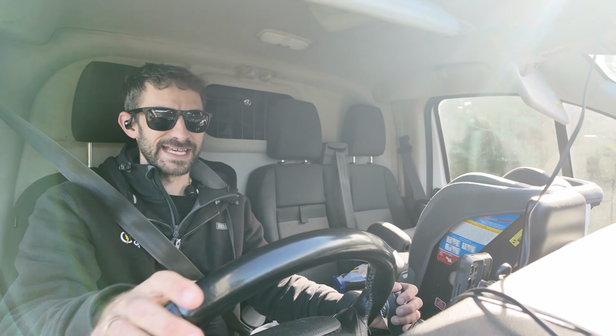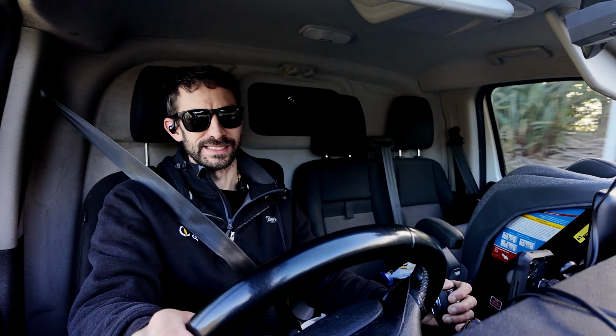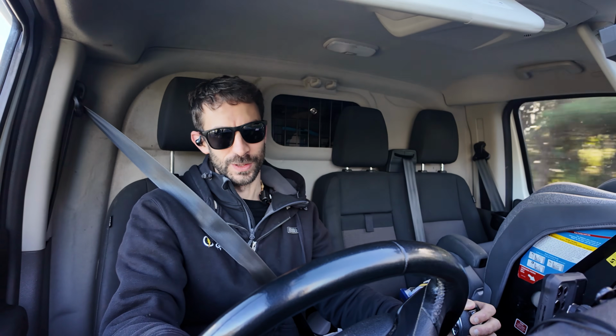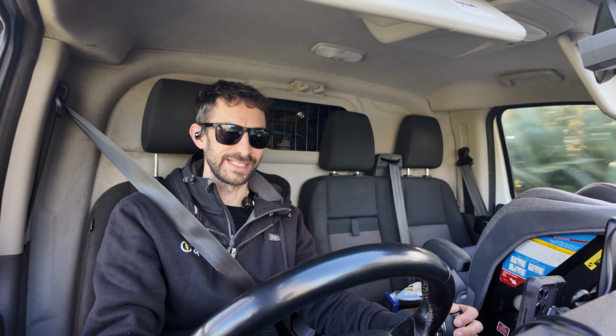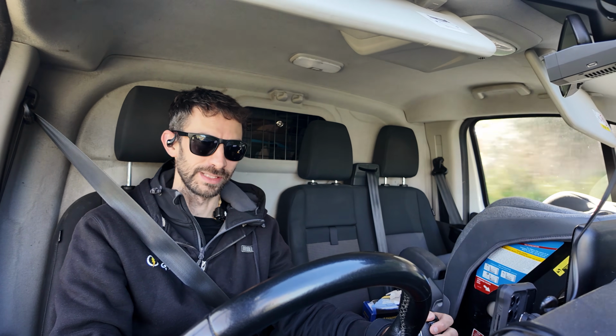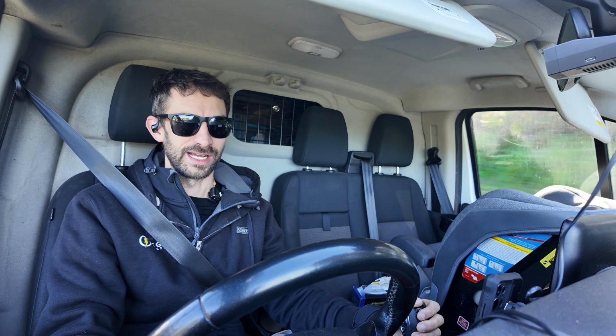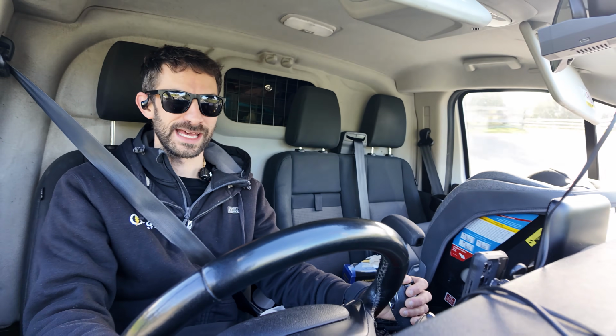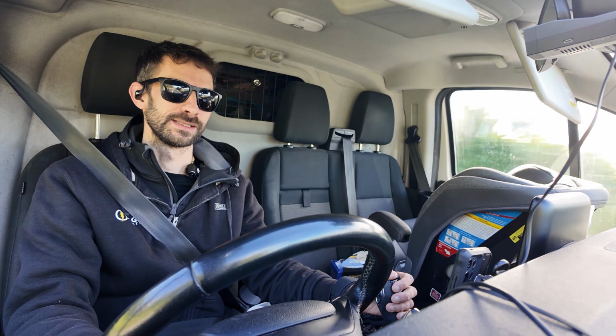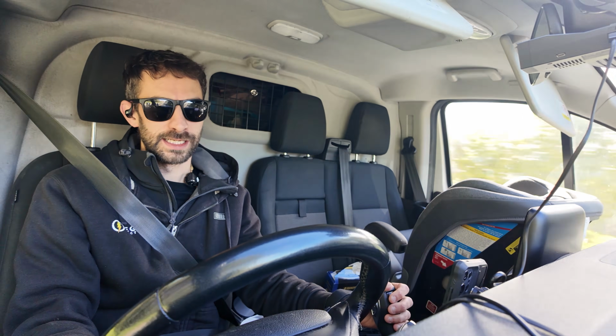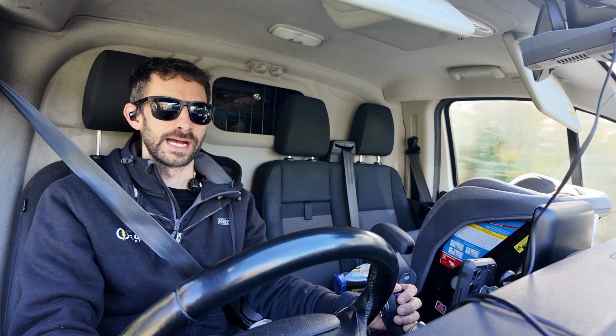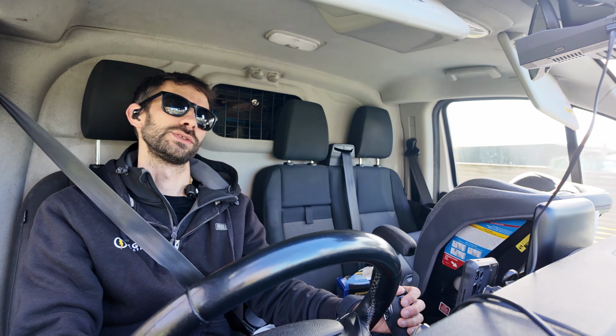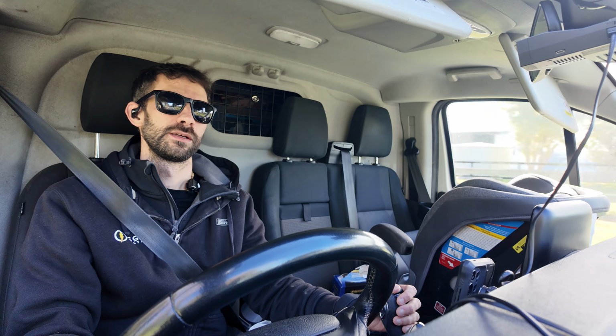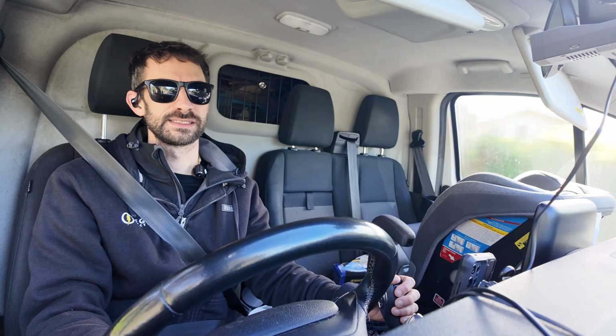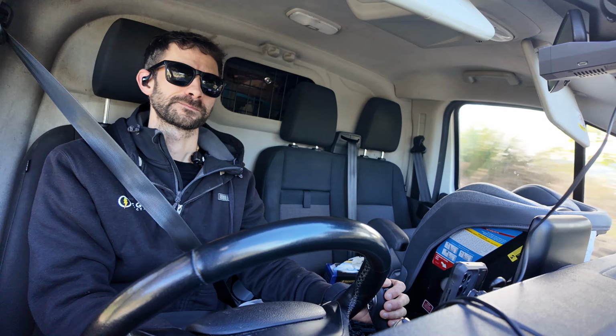I guess mistakes happen, but that's why we have testing. You make a mistake, and then before you finish your work, you go around and you check. And there's lots of testing the legislation requires, which maybe you can get away with not doing. But phase neutral transposition, the things that could create that are things you have to test. So back on, that was a bit of a side tangent. Yeah, the loss of the main neutral is the one single fault that the MEN system doesn't protect against.